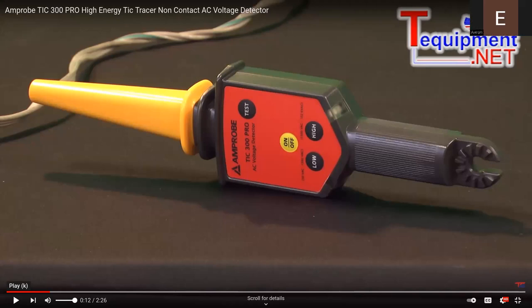Okay, so the biggest thing, and there are different models and everything like this. This was pretty popular. There's an older one called a Tic Tracer. Surprisingly, these things are really inexpensive. I think the Tic Tracer's down around $20 right now. Yeah, I got one in the back of my truck. I'll bring it. Yeah. So one thing he did include here is it's a proximity tester. You don't have to make contact to determine if the conductor or whatever you're working on has any kind of voltage on it. And usually what they'll do is they'll tick, or they'll make that beep, beep, beep, beep tone, and you'll see the pulse and the lights. And whenever you come close to a voltage, that beep will go solid. It will make a solid tone. And your lights will go solid. That should let you know that voltage is present. It will not let you know what the voltage is. You've got two different ranges there. You can use low, which is secondary voltages, and high, which is primary voltages.